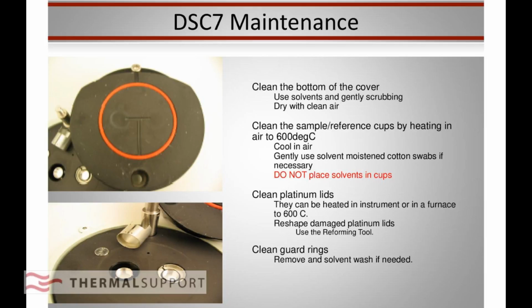1, clean the bottom of the cover. Basically anything that comes close to those little furnaces you want to make sure is clean. You can see the top picture there, there's a little stain. You clean that. That's right over the sample cell. You clean the sample and reference cups that you can see down here. Heating in air up to 600 degrees, you cool in air. If you got any debris in there, you can gently use a solvent and cotton swabs, but very gently. You don't see the platinum lids here, but there's one right down there. You want to reform those, and you want to clean those. They should not be all bent up.